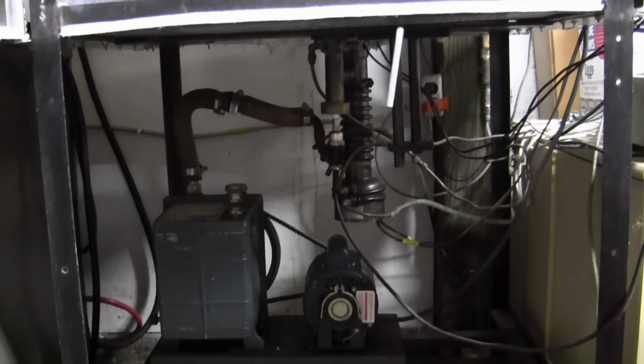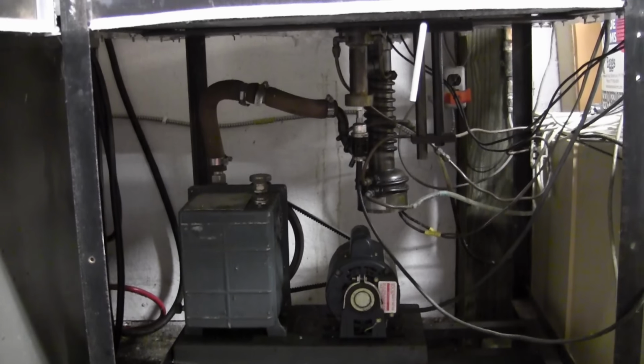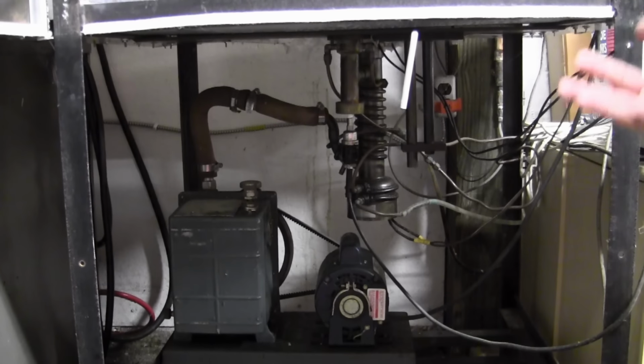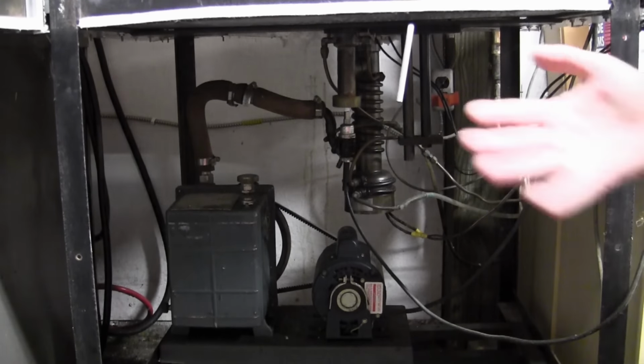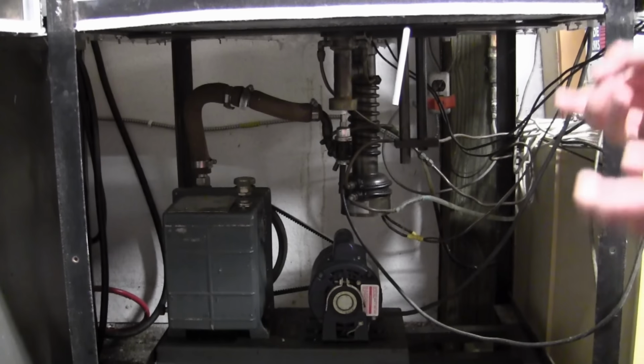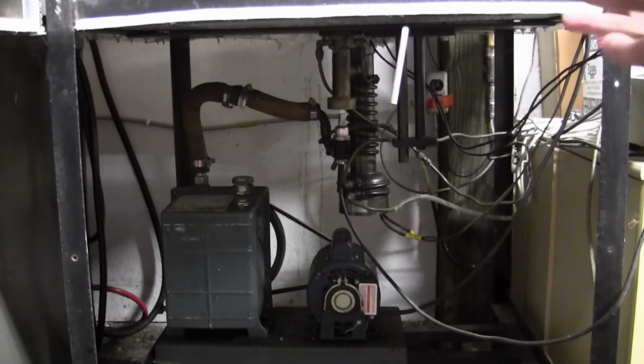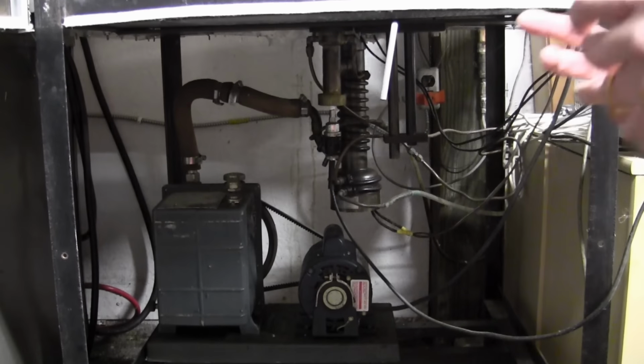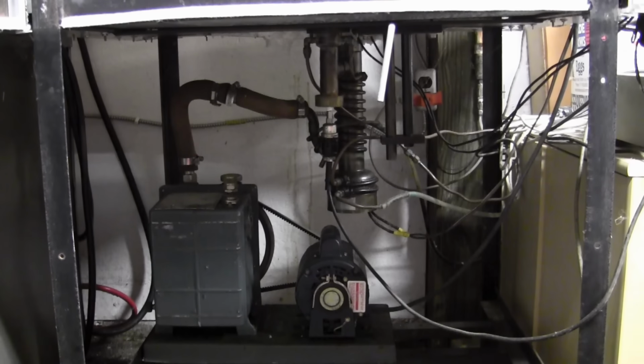But again, we're doing this while we're pumping. That's absolutely, totally dead critical, because if we don't pump and heat at the same time, we're not going to get all that residual gas that's adsorbed, not absorbed, into the surfaces of the inside of the tube.